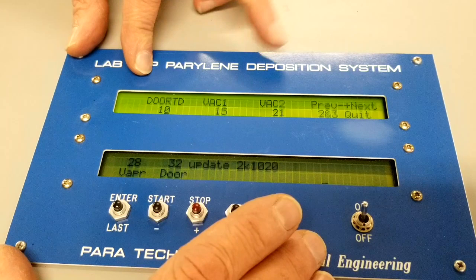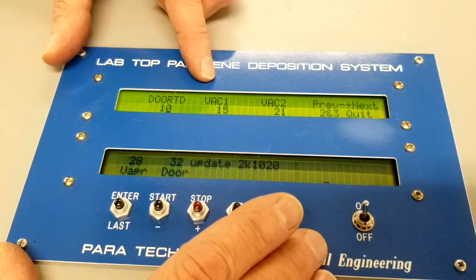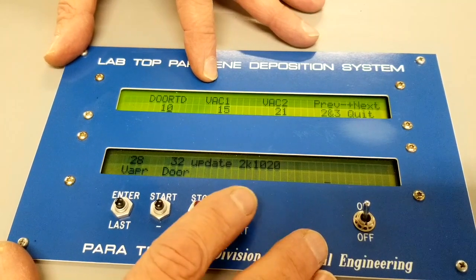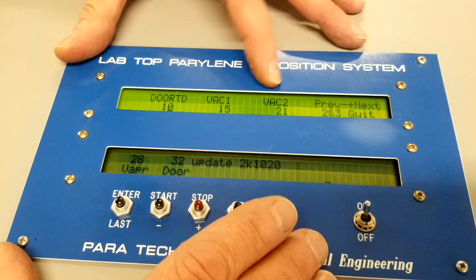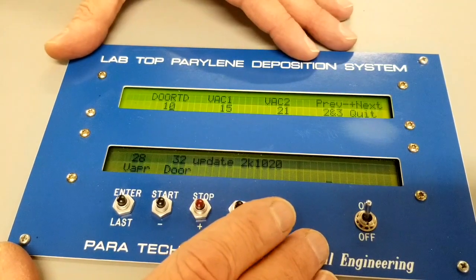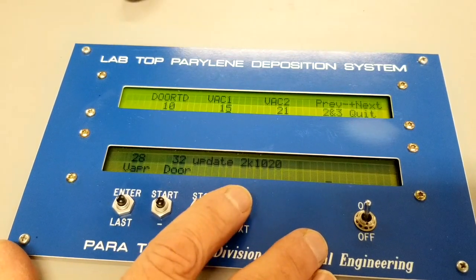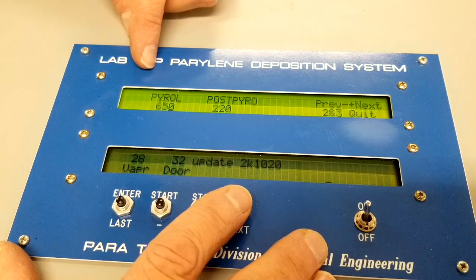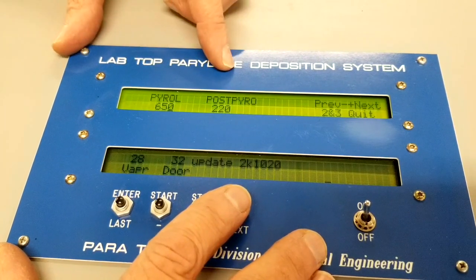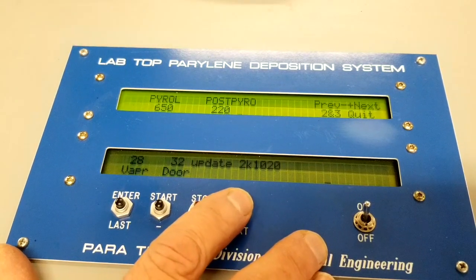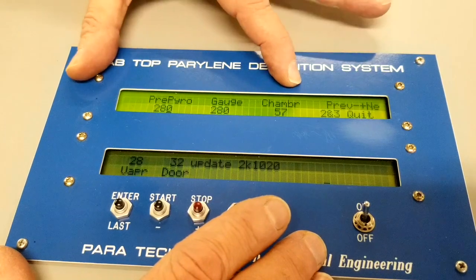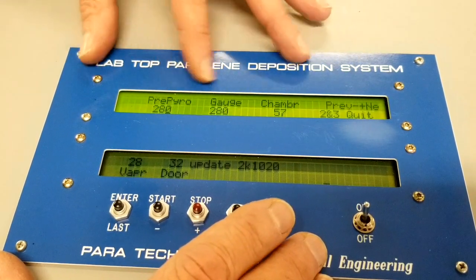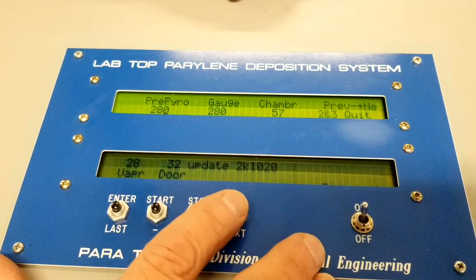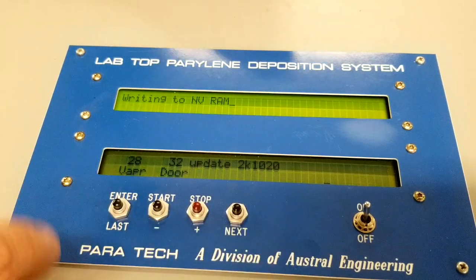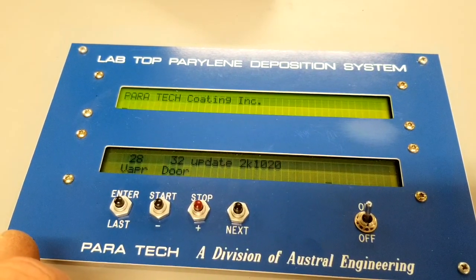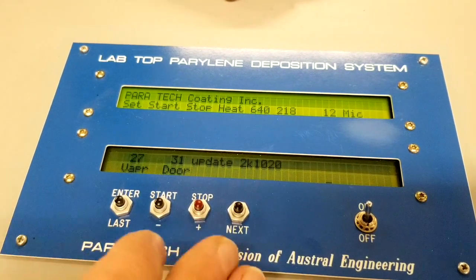The door is always 10 degrees above what the vaporizer is, so that's what that number indicates. VAC1 is how low it has to be before the start command will operate, and that's 15 microns. And then after the process is done, it'll pump down to 21, and then it'll turn off the vaporizer and door heaters. Here's where you set your pyrolysis tube temperature and your post-pyro temperature. So we're at 650 and 220. And then finally, there's 3 other pre-gauge and chamber. This unit does not have heaters for those, and this really has no effect on the system right here. So once we step through that, it's going to write and save that program every time you exit it. So right now we're loaded in with recipe number 2, as I just showed you.